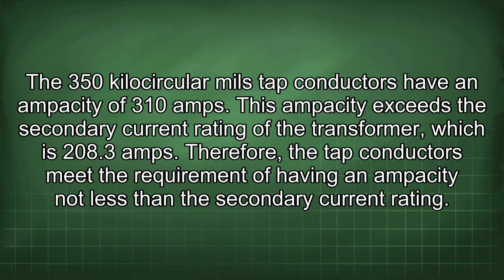The 350 kcmil tap conductors have an ampacity of 310 amps. This ampacity exceeds the secondary current rating of the transformer, which is 208.3 amps. Therefore, the tap conductors meet the requirement of having an ampacity not less than the secondary current rating.